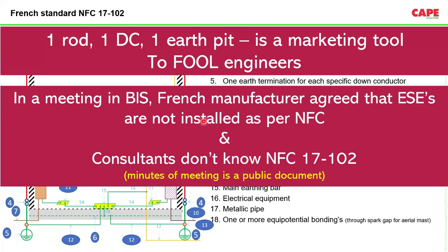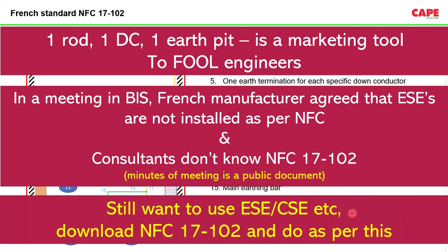So one French manufacturer agreed that ESEs are not installed as per the national French code. They said that yes, there is a French code and you are supposed to use it as per the French code. But in India, nobody uses ESE as per the French code, and they also blamed that the consultants don't know about the French code. As a result, the consultants are responsible for the one rod, one down conductor, one earth electrode. Consultants or the safety auditors are responsible, and the manufacturer is not responsible. Basically, they made the story of one rod, one down conductor, and one earthing, sold it, and finally they say, I'm not responsible. If you still want to use these non-standard items, please download the National French Code 17102, then do as per this particular code. Don't believe the manufacturer's claim of one rod, one down conductor, and one earth pit, because it is just to fool engineers and to make business.